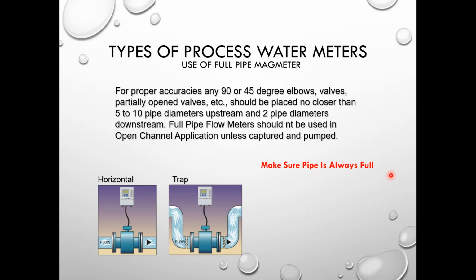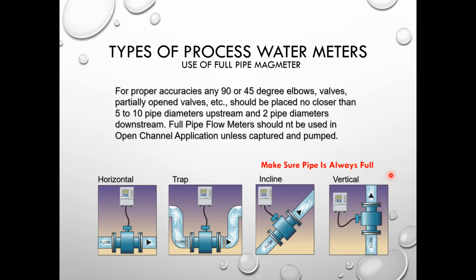So for types of flow meters, what we've seen in the market is full pipe mag meters used on effluent lines. The biggest limitation is that it's only measuring velocity, so you've got to make sure that your pipe is always full. You want good straight runs coming into your mag meters, and you want to make sure they're always clean, that there's not a lot of debris stuck in there. I have seen this type of model where the liquid depth is half here, it drops down into a P-trap to create a full pipe, and then it comes back out into a gravity situation. This type of situation does not work very well.